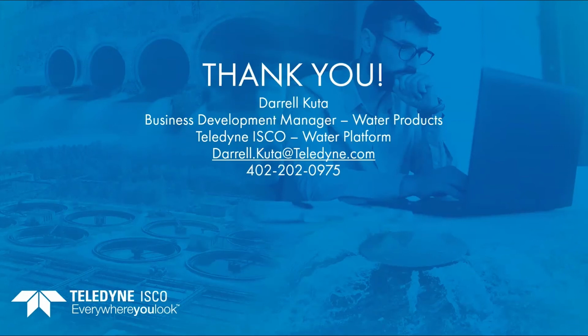One thing I caution against is going out there and calibrating every time when it's only off by a little bit, because sometimes you end up just chasing a calibration. One time somebody goes out there and adjusts a little bit higher. The next time they adjust it about the same amount lower. So you keep chasing that calibration back and forth, and you just want to be careful of that. That's especially true at locations with a steep slope, where you have low level and high velocity. It makes it really difficult to calibrate. And so that's where you want to use the open air techniques, or try to calibrate in the open air.